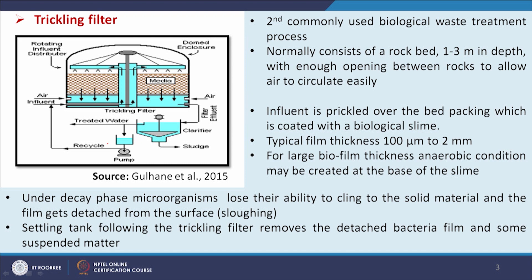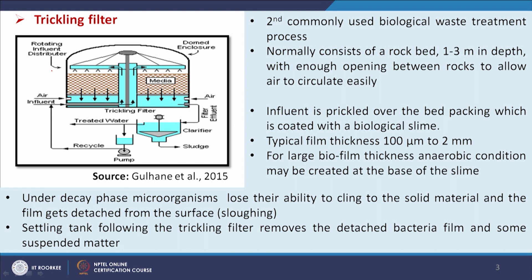In the trickling filter, a microbial layer is formed on some solid support, and then water is passed through it. The microbes work on the organic compounds present and degrade them, purifying the water. Aerobic conditions are provided; water is passed from the top and there is a microbial layer developed on the media material.